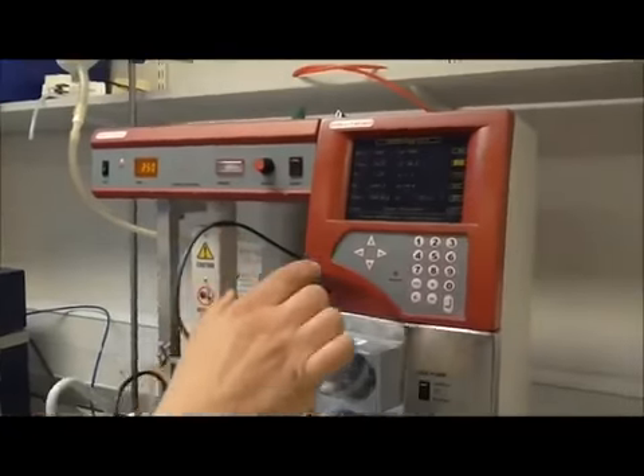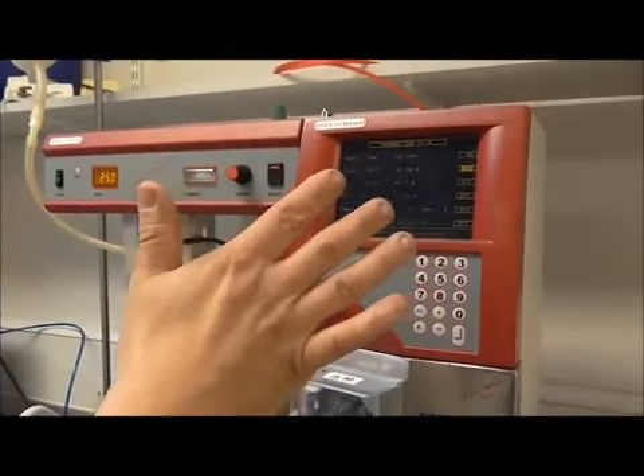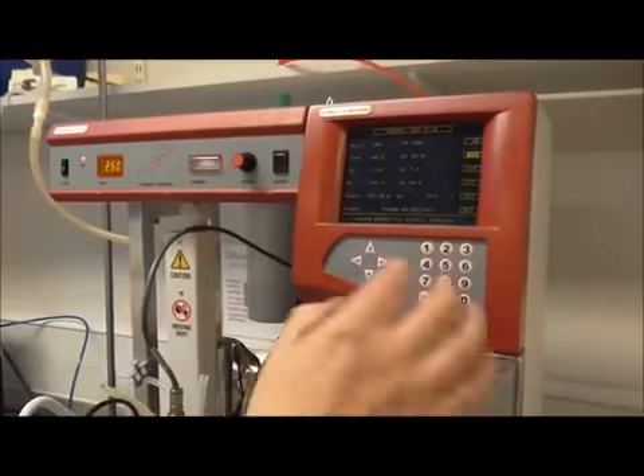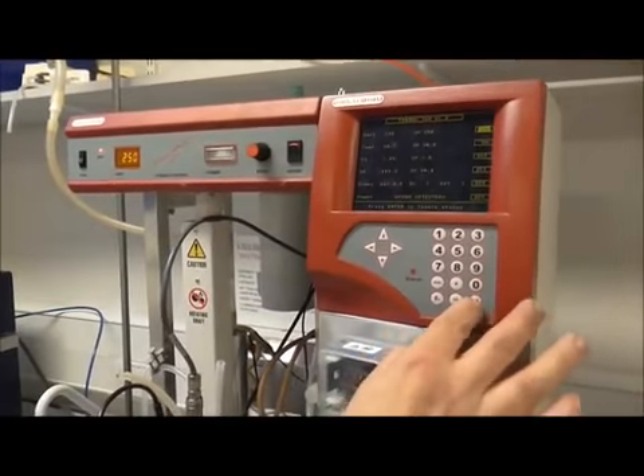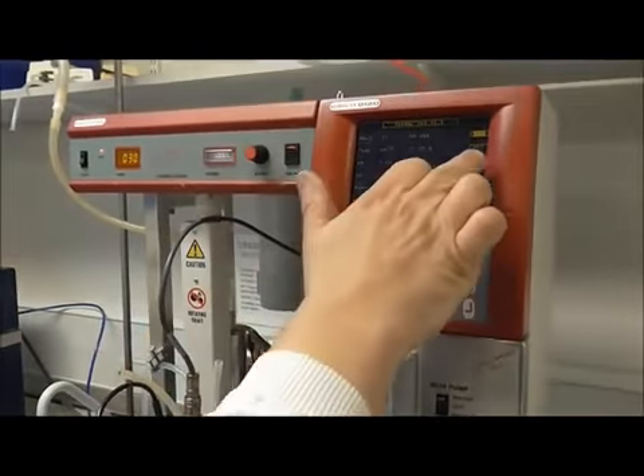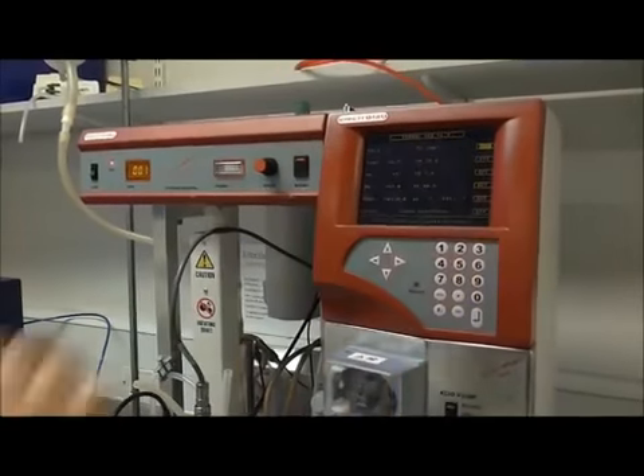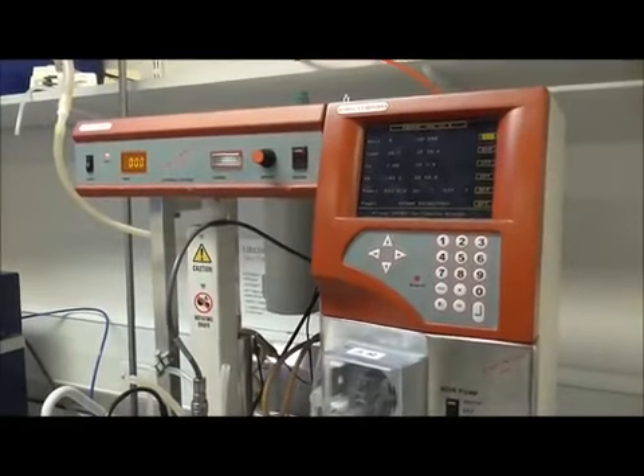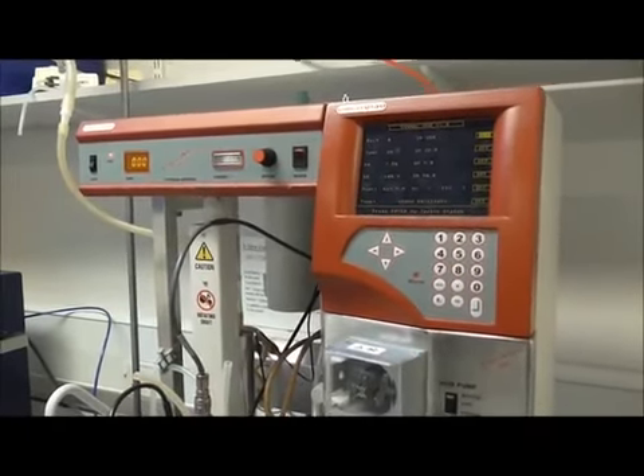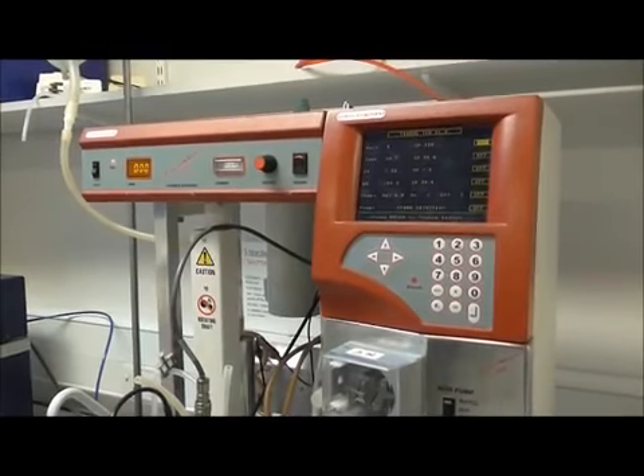The temperature is interlocked with the agitation, so if for any reason you switch off the agitator, then it'll automatically cut the power to the heating mat. It's a safety device because you don't want this red hot whilst you're sort of taking it off.